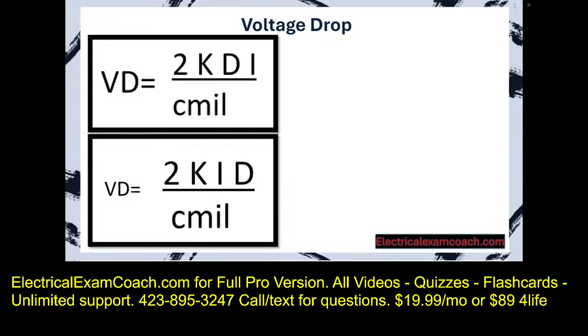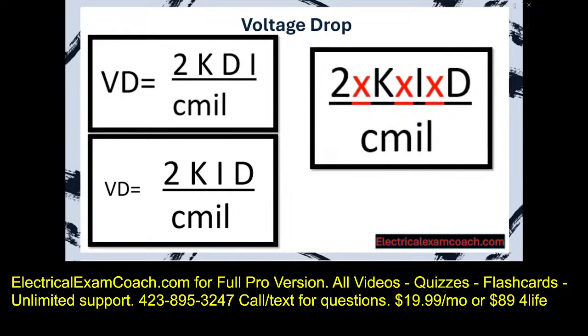2KID over C mil. Easy to remember and easy to plug in. And what this is, just like previously in the program, is implied multiplication. So it's going to be 2 multiplied by K, multiplied by I, multiplied by D, divided by C mils.